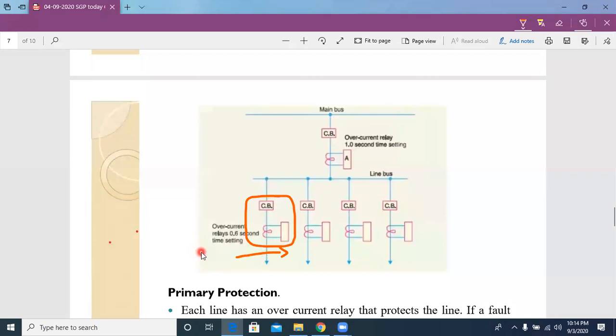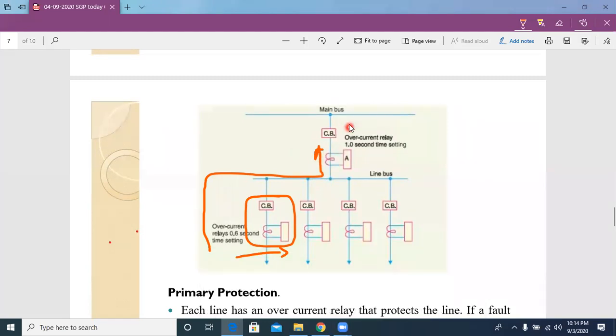So what will happen immediately? The fault current directly enters the feeder section because of this misbehavior of the relay. This fault current is very dangerous. It may damage the feeder and also the main bus. At that time we need to prevent this fault current from damaging the feeder and main bus. That's why we place one more relay here.